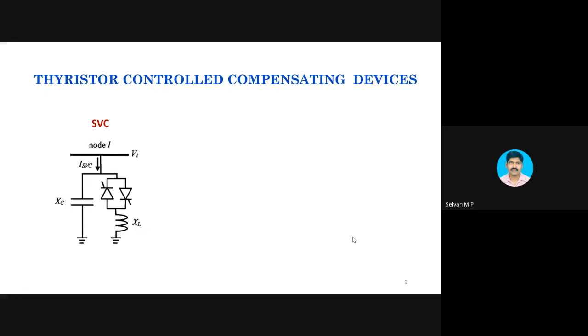The first one is the SVC, static var compensator. Var means reactive power, volt ampere reactive. Compensator, because the reactive demand is compensated by this device. Actually, we don't call it a source, because you know that reactive power is not used. It is actually flowing from one component to another, right? That's why it is called a compensator.